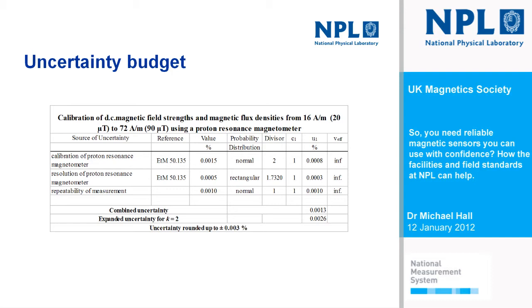When we use a Helmholtz coil to generate, we of course measure, so this budget applies, and we have some additional terms for measuring the current that goes through the winding and on the actual determination of the coil constant. Very low uncertainties, which provide a very good basis for calibrating flux gate magnetometers, as well as other very sensitive magnetic sensors, such as those based on GMR, GMI, and other quite new phenomena based on magnetic thin films.